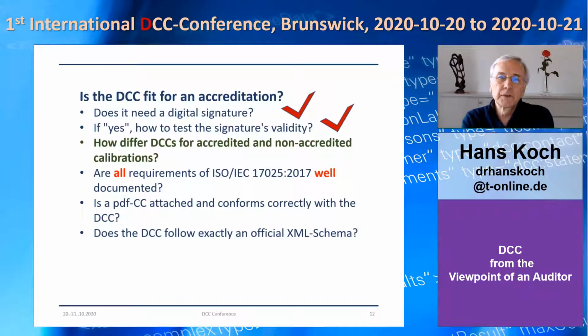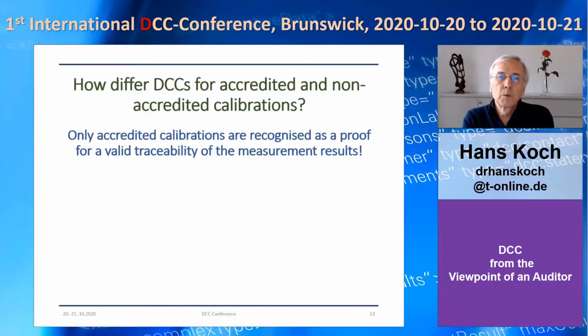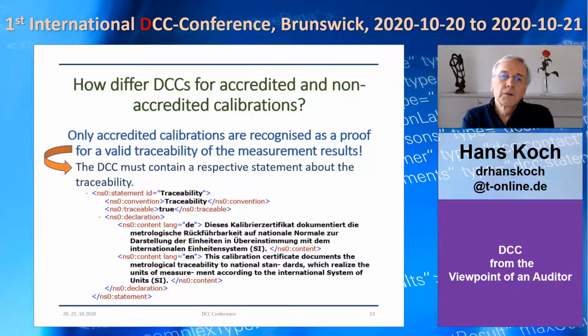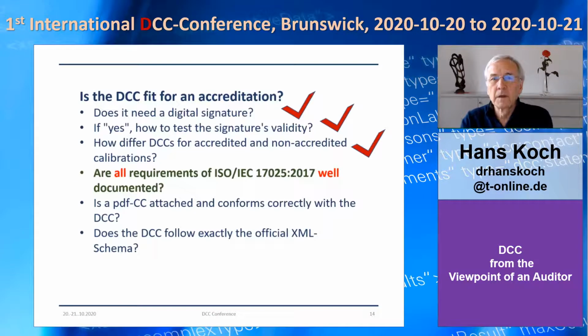Now, what is the difference between an accredited and a non-accredited calibration? Well, only the accredited calibrations are recognized as a proof for a valid traceability of the measurement results, not the works calibration. So the DCC must contain a respective statement about this traceability, and an example is shown here of how to do this. So this point we also touched.